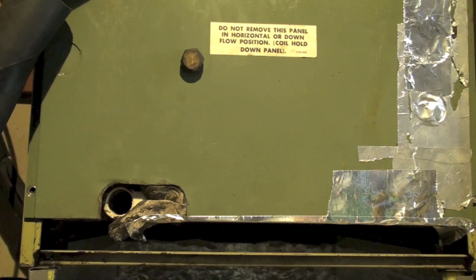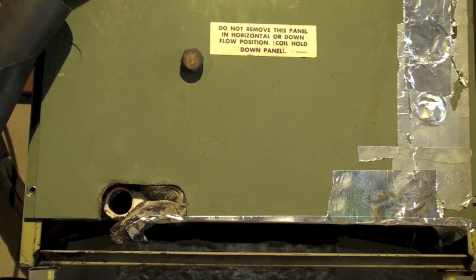I've been asked how the P-trap works on the air conditioner evaporating coil. The issue here is if you look at that fitting up there, that's under a negative pressure and it's going to pull air into it. When it pulls air into it, it tends to keep the condensate inside.